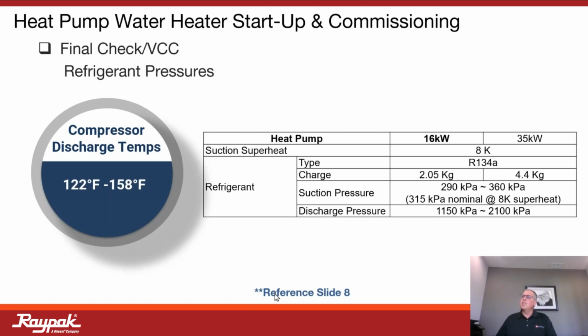So again, we can reference slide 8 that we talked about earlier, but we're also going to talk about a consequence. If you're doing a startup and commissioning, we can go on and look at that display screen and register what our Fahrenheit temperatures are, as well as what our pressures are. And we can note a consequence. If we have an undercharge or correct refrigerant pressure or overpressure, it's going to manifest itself in a couple of ways. So we do have a guide here that we can reference for what that cause and effect will be. If we have an overcharge, too much refrigerant in the system, here's how it's going to manifest itself. Here are those numbers that we're going to look for on this screen.